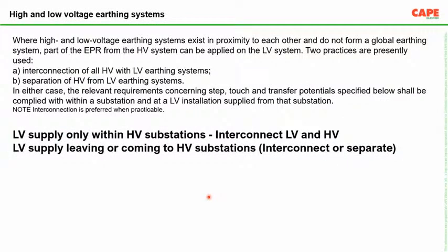Now I will skip this. There are the concepts of how high voltage and low voltage earthing are handled. Basically, for low voltage supply confined within the high voltage substation, their interconnection is mandatory. For a low voltage substation, there are two choices: interconnection and separate. Interconnection and separate means the low voltage earthing and the high voltage earthing you can interconnect, or you can separate under certain conditions.